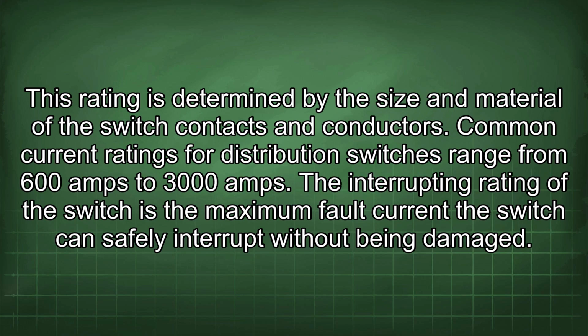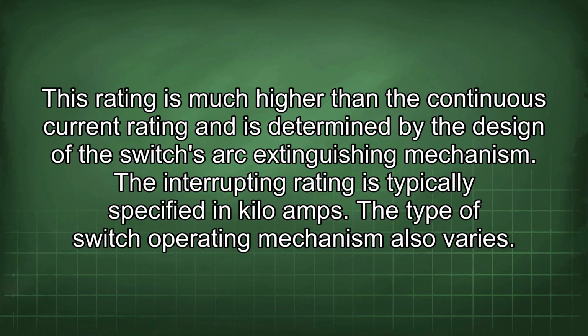The interrupting rating of the switch is the maximum fault current the switch can safely interrupt without being damaged. This rating is much higher than the continuous current rating and is determined by the design of the switch's arc extinguishing mechanism. The interrupting rating is typically specified in kiloamps.